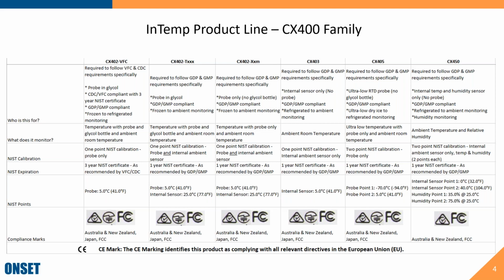It does not require probe and glycol, but a logger in general that has a 1-year NIST certificate. So that is a key differentiator there. If you're following GDP, GMP guidelines specifically, they are saying to go with a 1-year NIST certificate. And we NIST both the probe and the ambient sensor for that one. So that is the major difference there.